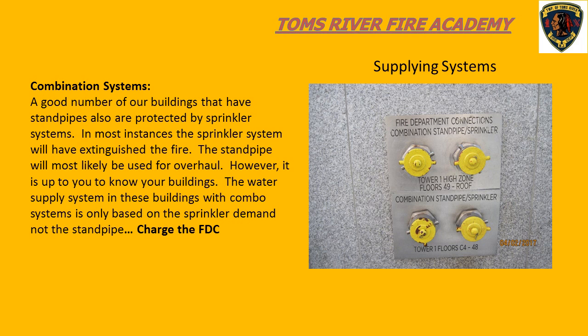Sometimes you'll see signage for combination systems. It's basically going to tell you that that fire department connection is servicing a different area of the building. It may be only servicing a standpipe, it may be servicing just a sprinkler, it may be servicing only certain areas of the building. So just be cognizant that if there's signage on or near the fire department connection, you take a look at it so you know what area of the building you're pumping to. This mainly pertains to larger buildings.